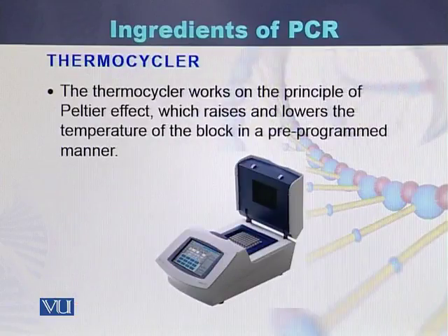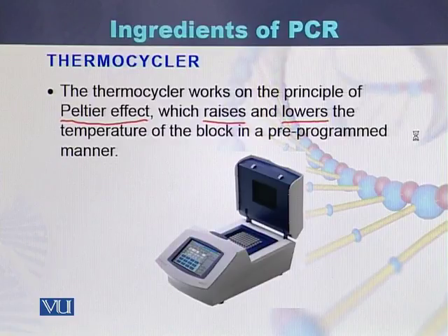The next is the thermocycler. Thermocycler is also called a PCR machine. Thermocycler works on the principle of the Peltier effect. The Peltier effect is that by which the temperature rises and lowers. Once we have to increase the temperature, and during the next step we have to decrease the temperature, such a process is called the Peltier effect. So the Peltier effect raises and decreases the temperature in a block. This is the block of the PCR.